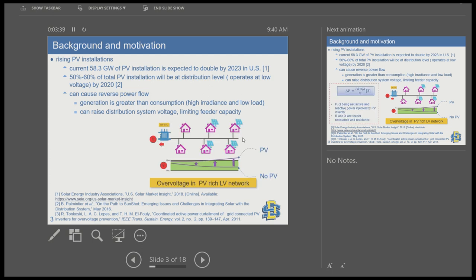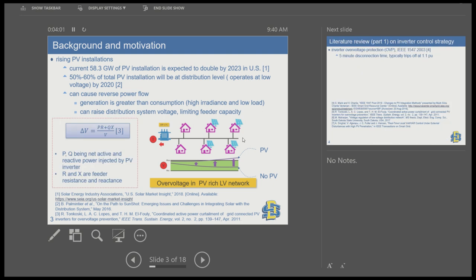To give you an idea: in a distribution network with no PV, there is no reverse power flow and the voltage is expected to drop down the feeder. But when there is high PV installation, the voltage can go up, causing overvoltage in the low-voltage feeder. The typical relation for overvoltage with respect to the amount of power injected at a node is: where P is the net active power injected, Q is the net reactive power injected, R and X are distribution parameters, and V is the voltage. The voltage rise is directly proportional to the amount of power injected.